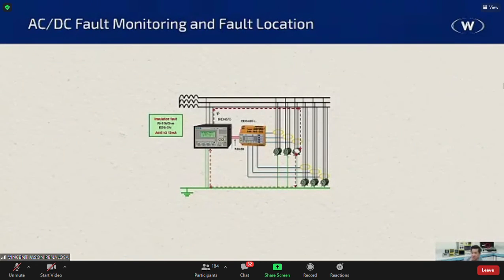So if this were a DC circuit, what's going to happen is basically it's going to tell you whether it's on the positive side or on the negative side. And it will give you the exact location where it is. Now, that would be basically a conceptual model of how it works. The measuring principle is going to be exactly the same for critical care units of hospitals, only with a few differences in terms of specifications and thresholds and limits.